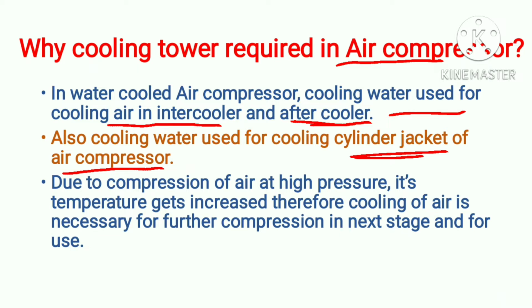Therefore, cooling of air is necessary for further compression in the next stage and for use. If you do not cool the air in the intercooler or aftercooler, then our air compressor efficiency will be very low. Therefore, for increasing the efficiency of the air compressor, we cool the air in the intercooler, and in the aftercooler we cool air for use in instruments and for other applications. So this is the purpose of cooling air in an air compressor.